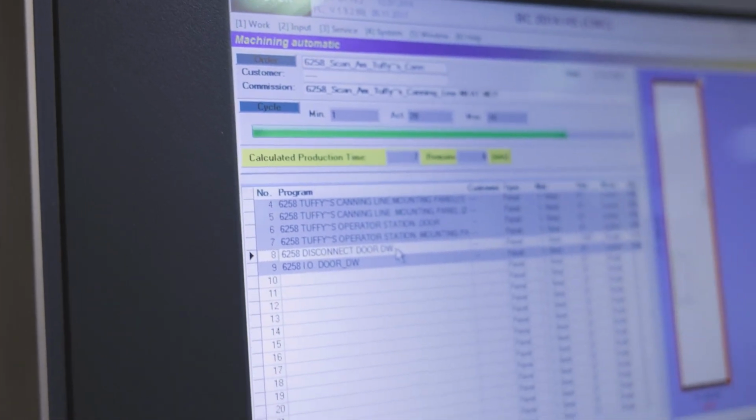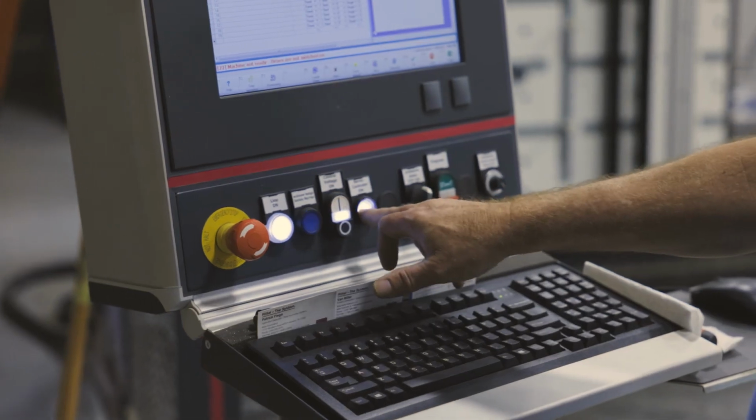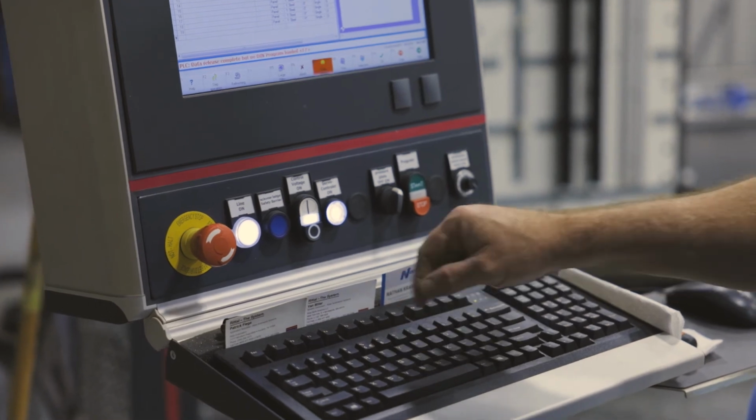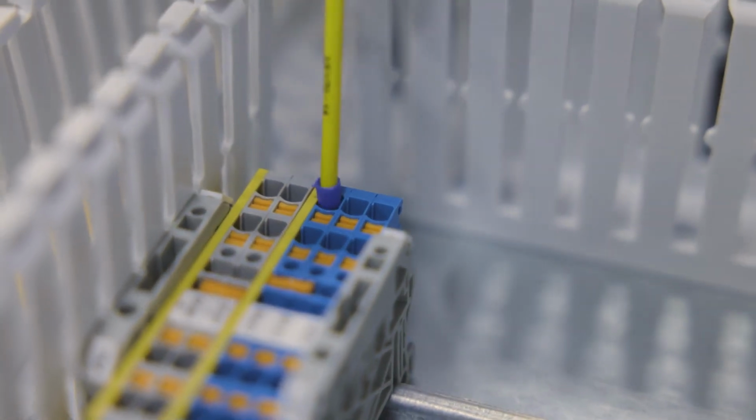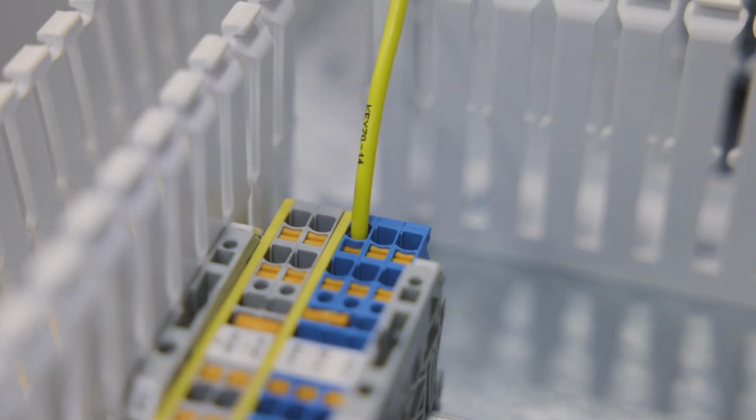When you run a back panel on our Perforex, all the wire shavings actually fall off of there. We can sweep it off. There's no chance of ever having one of those fall into the top of your drive and then blow up a $10,000 drive. And then you go all the way down to like the push-in terminal. You pair those with ferrules, and now a plant doesn't have as much maintenance later on. They don't have things that are loosening up over time as you have those interactions with vibration and thermal expansion or whatever. I mean, all that stuff is the unseen benefits that someone is getting out of all this.